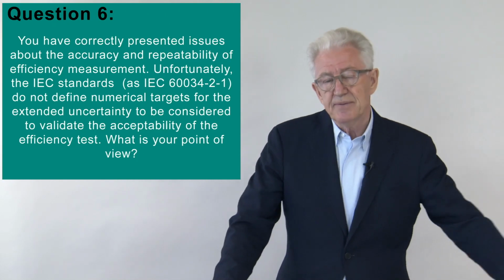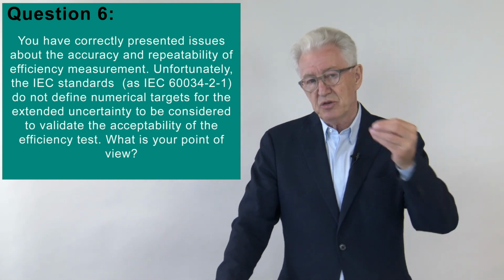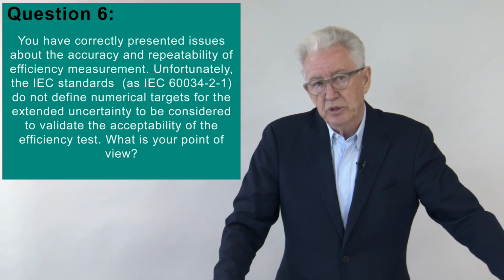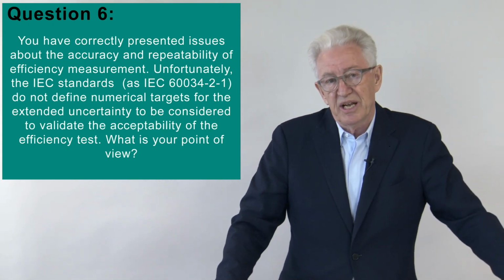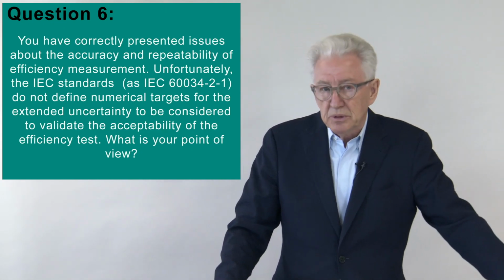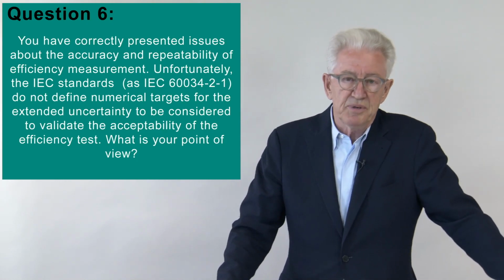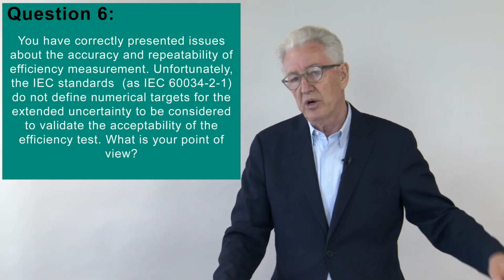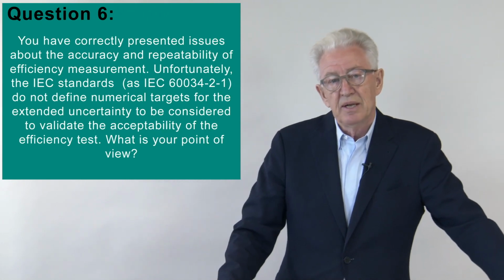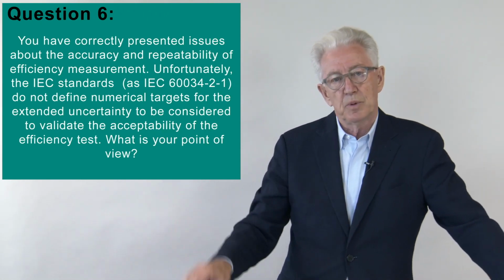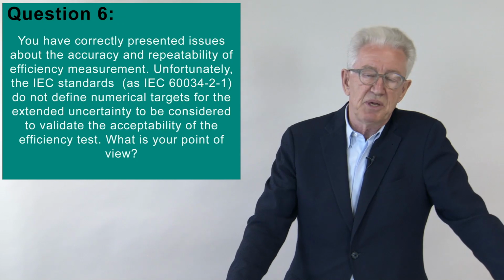That's the quality control of the manufacturer. The other thing is the quality of the measurement. When you measure a motor's performance, you have some critical elements. You have to measure the electric input, which is usually relatively precise, but you can have harmonics in the domain, and you measure the mechanical output, for which you need a torque meter and a speed meter.